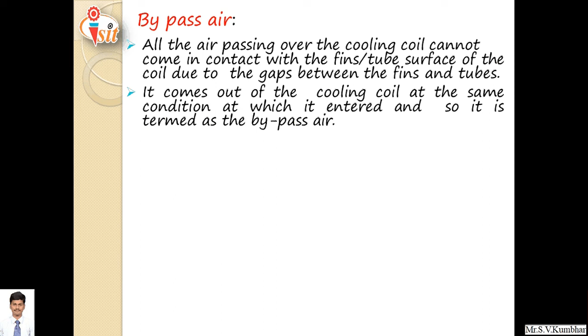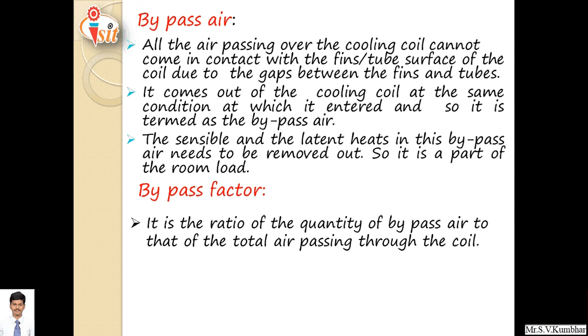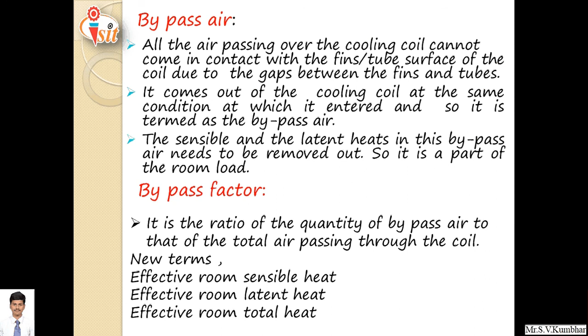Bypass factor is the ratio of the quantity of bypass air to that of the total air passing through the coil. If you consider a cooling coil, bypass factor is defined as the ratio of the quantity of air which is bypassed to the total air passing over the cooling coil. There are a few terms related to this: effective room sensible heat, effective room latent heat, effective room total heat.